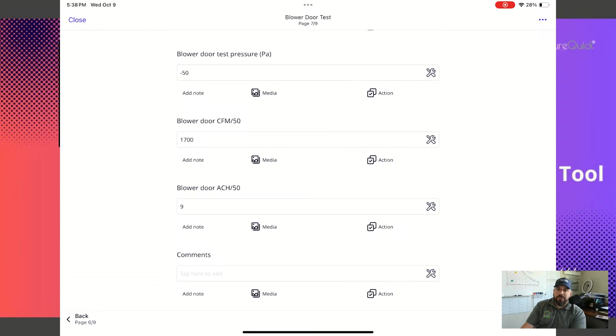test for a Manual J purpose, you're supposed to block off your ducts, because if you don't, you are including duct leakage with your envelope, and so you're kind of double dipping with duct leakage and envelope leakage. So when I do that blower door test, I have already taped up all my supplies and returns. Now I go ahead and do a duct leakage test. So those are two separate tests, and I'm quantifying what my duct leakage is. Go ahead and keep playing.